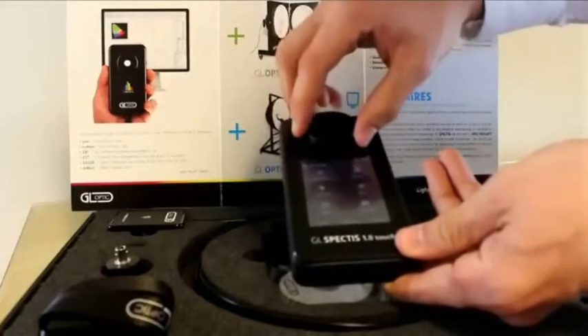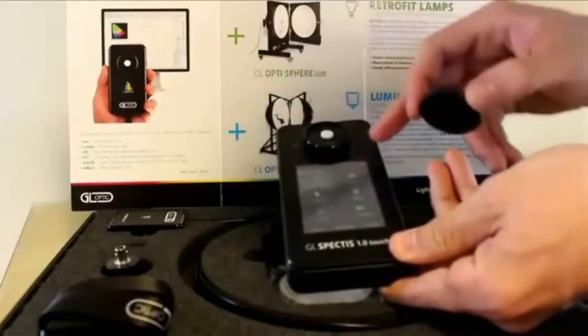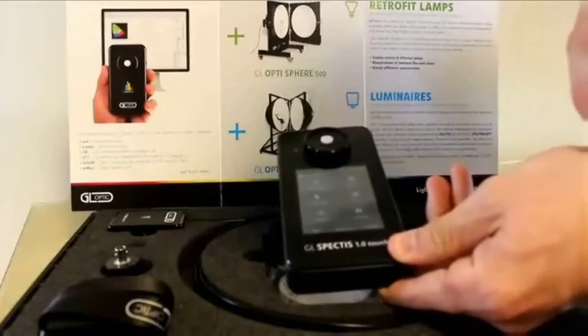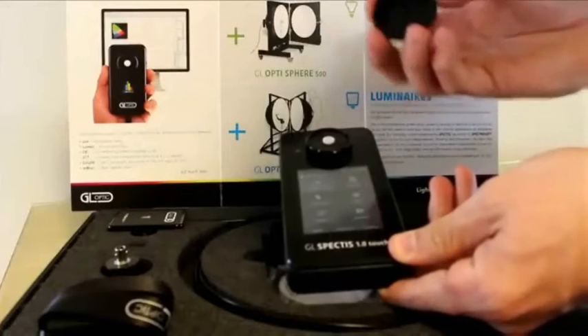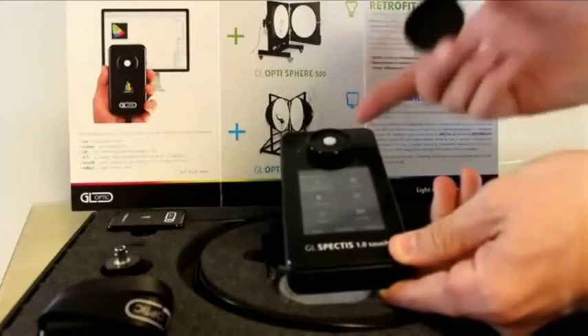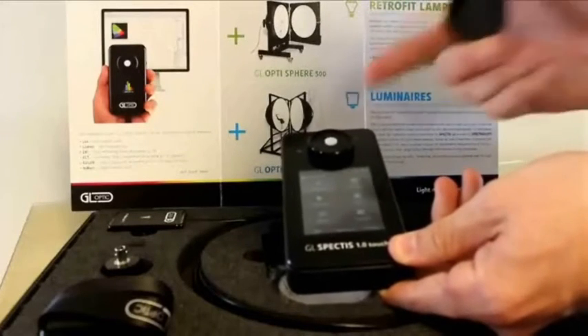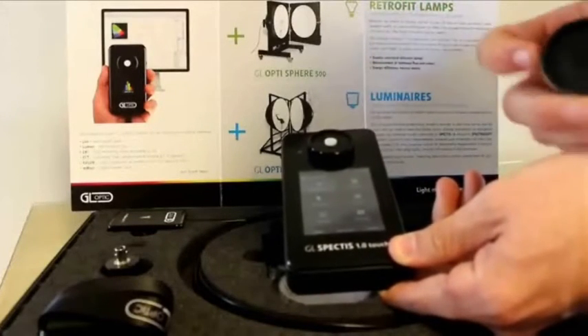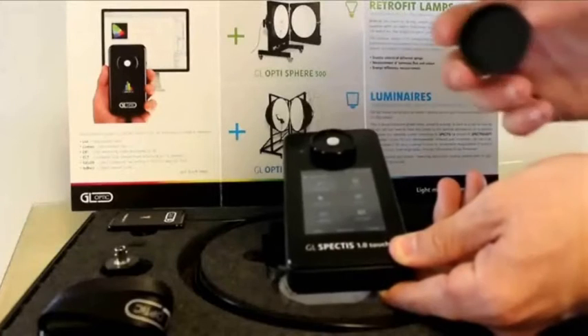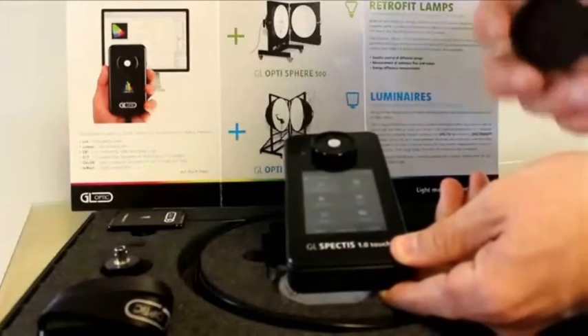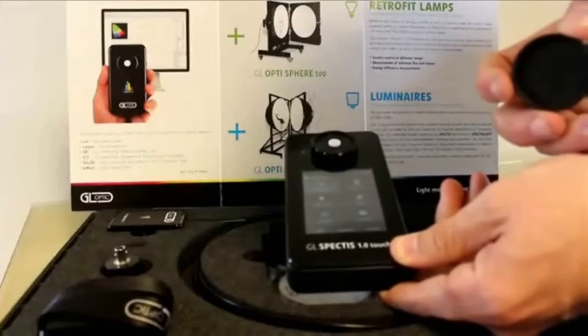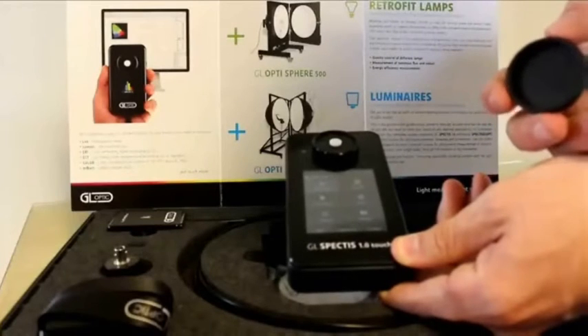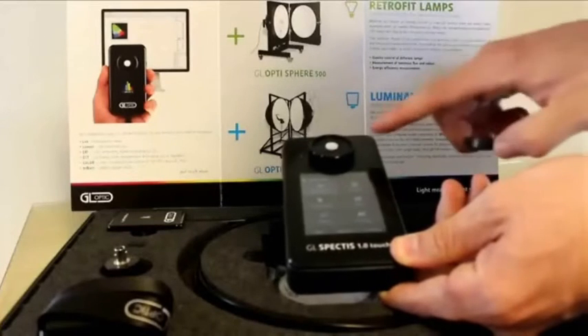Finally, we have a cap here, which is protecting our cosine corrector receptor head. This has two uses. One is to protect the cosine corrector head. The other is to perform zero-out dark current calibrations on the device, which need to be done every month or so.